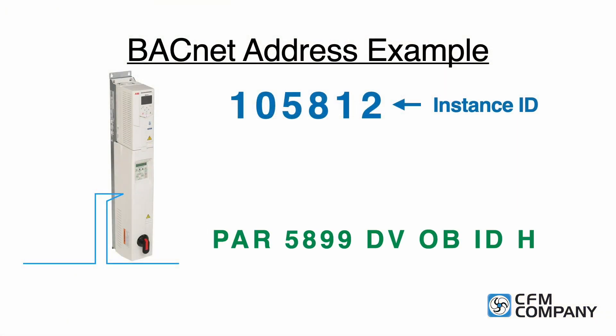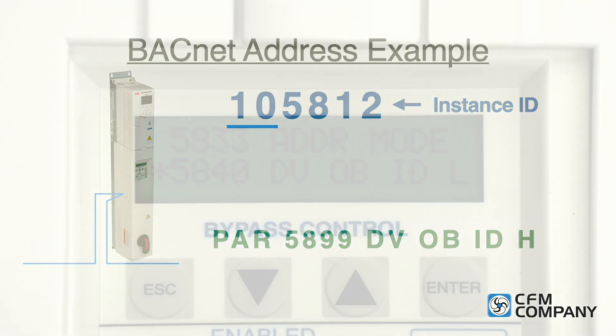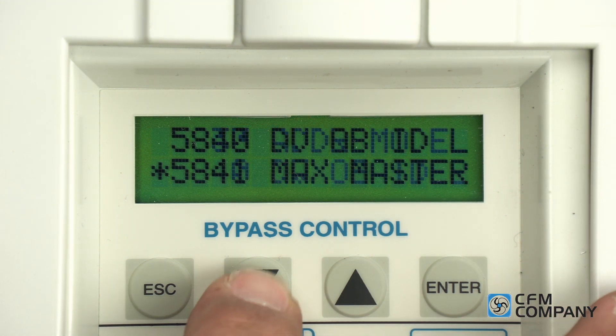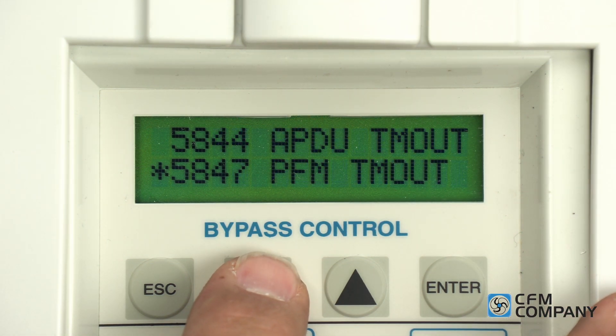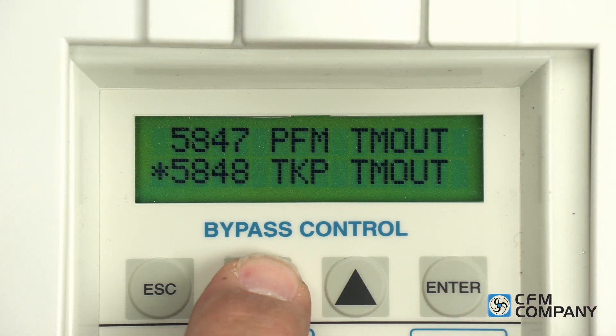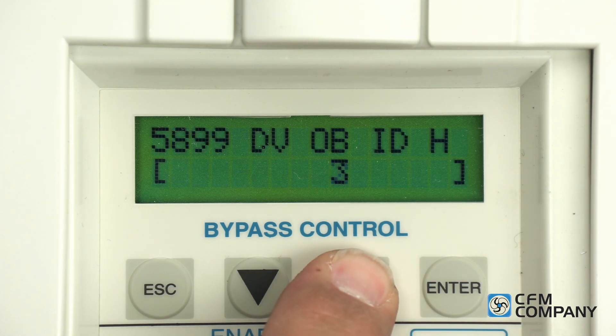Next, enter the drive's object ID high value. The object ID high value will be the remaining digits to the left of 5812, which is 10. Navigate down to parameter 5899 dvobidh and press enter to edit. Use the up arrow to enter 10 and press enter to save the value.